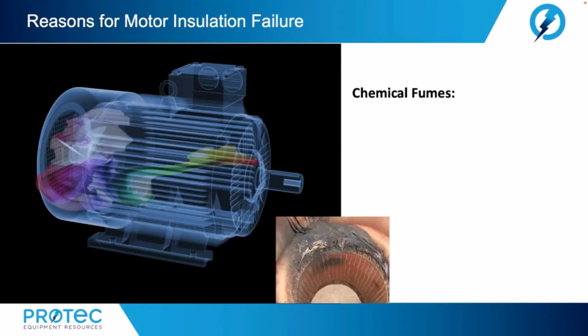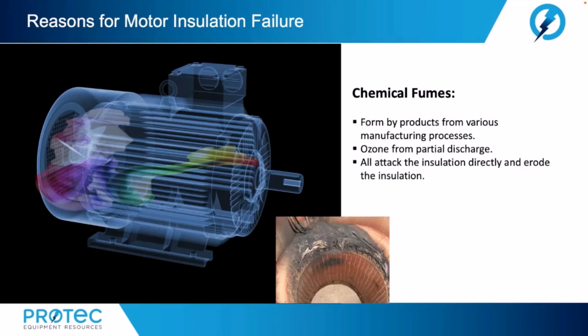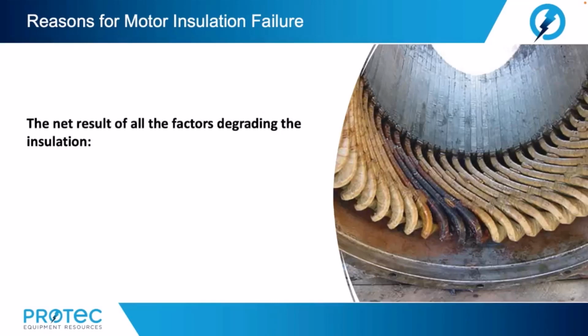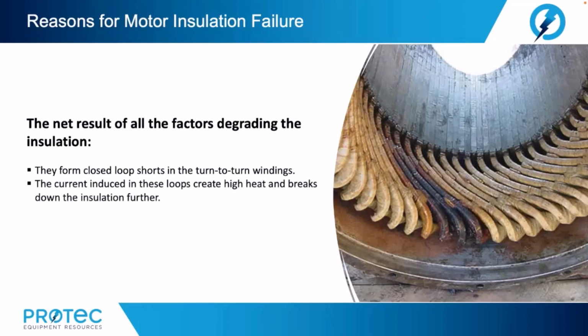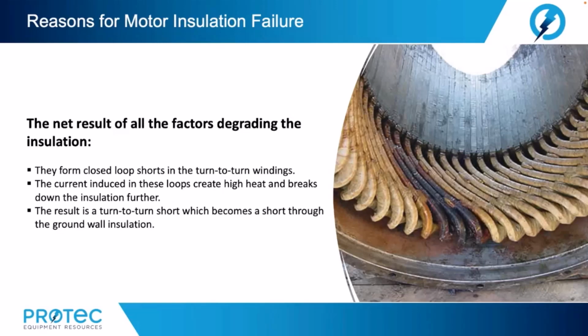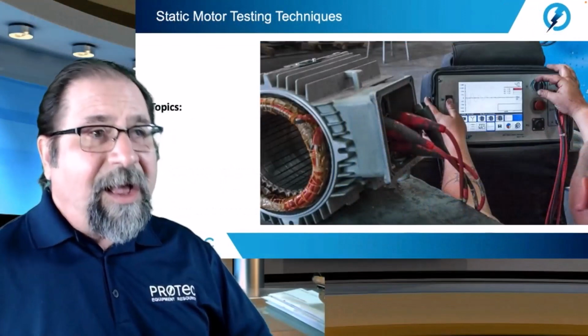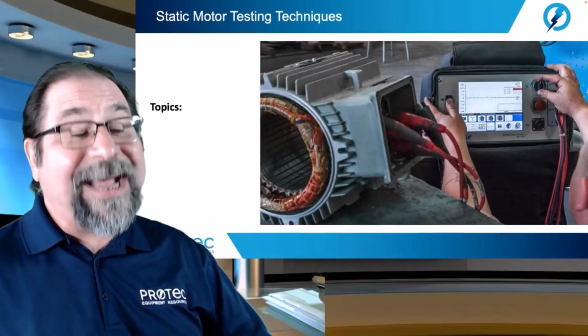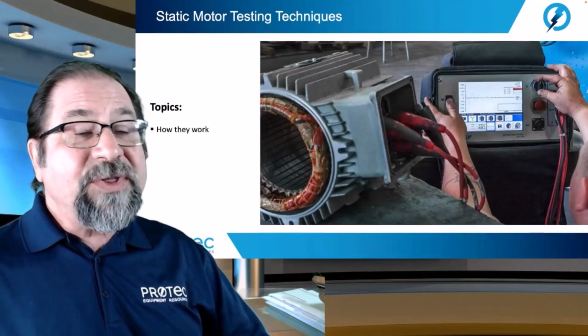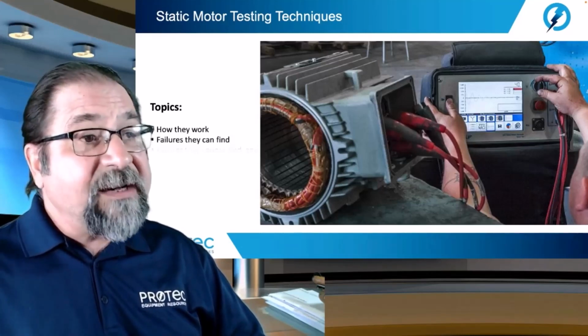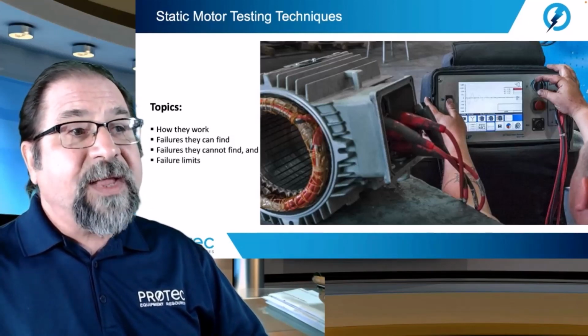Now let's focus on those chemical fumes. They form as byproducts from various manufacturing processes, or from ozone from partial discharge. All attack the insulation directly and erode the insulation. Now, the net result of all the factors degrading the insulation: they form closed-loop shorts in the turn-to-turn windings. The current induced in these loops create high heat and breaks down the insulation further. The result is a turn-to-turn short, which becomes a short through the ground wall insulation. All right, now let's move on to the static motor testing techniques. The topics here that we're going to cover: how do the techniques work, failures they can find, and failures that they cannot find, and failure limits.